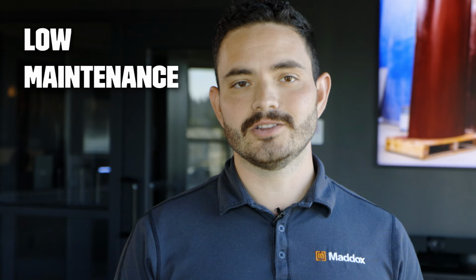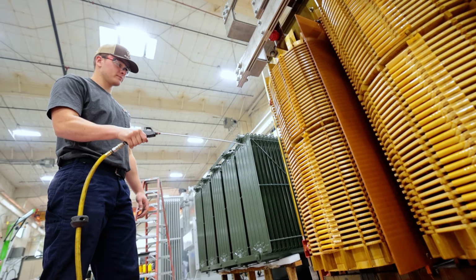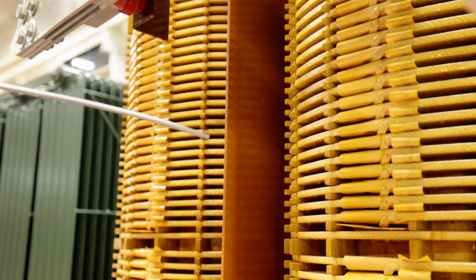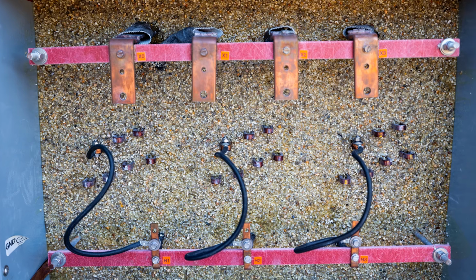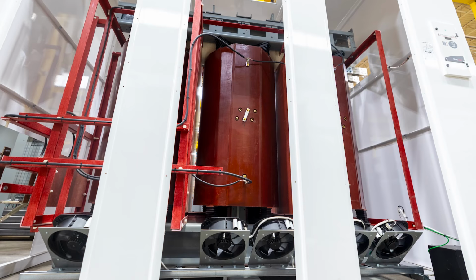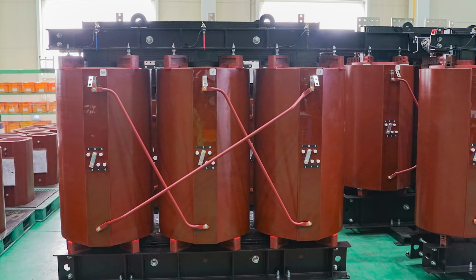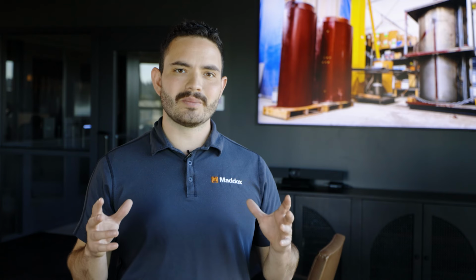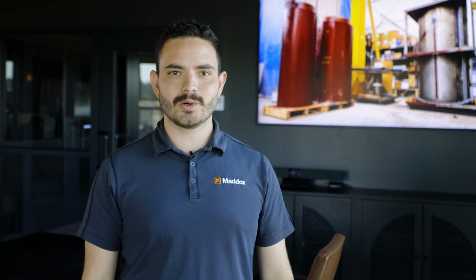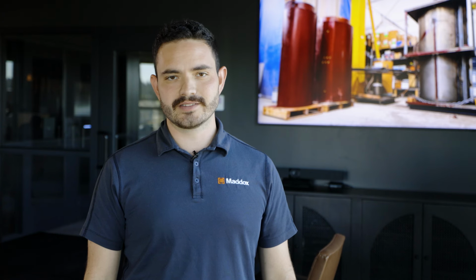And lastly, low maintenance. A big part of dry type maintenance is clearing the dust and debris from the windings. Cast resin transformers prevent both of those elements from reaching the windings. The resin barrier minimizes the need for maintenance around the coils. It's important to remember that you will still need to clear out your cast coil enclosures from any dust or debris that finds its way into those.